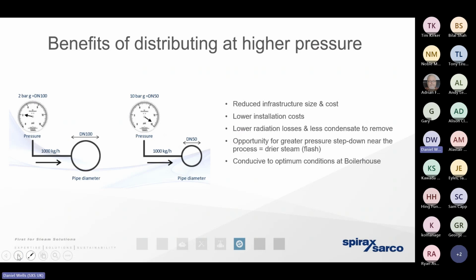So one of the best things that we need to understand is the benefit of not only generating high pressure steam, it's in distributing high pressure steam as well. Simply put, high pressure steam with a small volume is going to help us keep the infrastructure small, but it also means that we can reduce the size of the pipework, which means we've reduced the mass of that radiator. We've reduced the heat loss. So we don't need as many steam traps to remove the condensate. We're going to get more steam finding its way to the process. We've got drier steam, so there's more energy in the steam, so the boiler doesn't have to work harder.